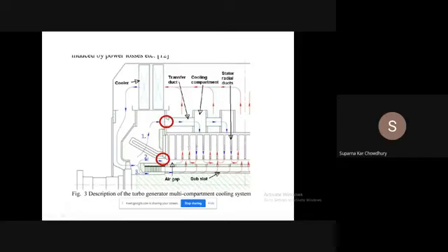Whether it is air or hydrogen, the phenomenon of corona is there, but the adverse effect of corona in the case of hydrogen is limited because there is no oxygen and nitrogen. So it is advantageous to have hydrogen as a cooling medium. So for large machines, we have hydrogen as a cooling medium.